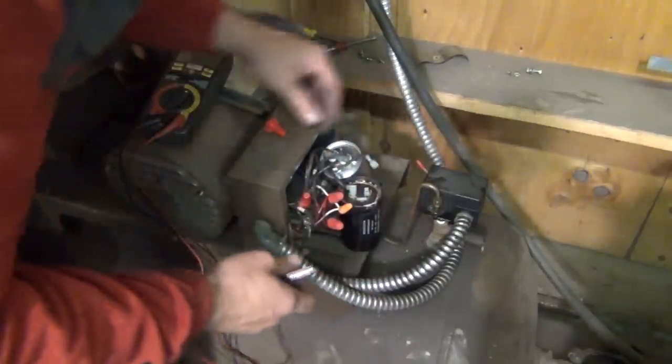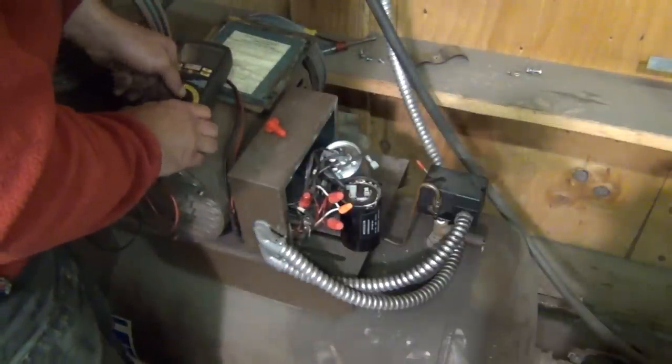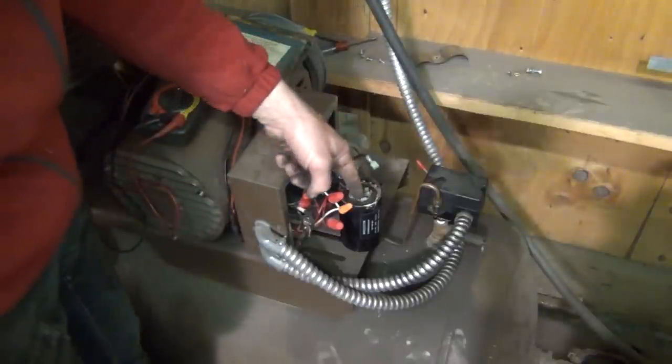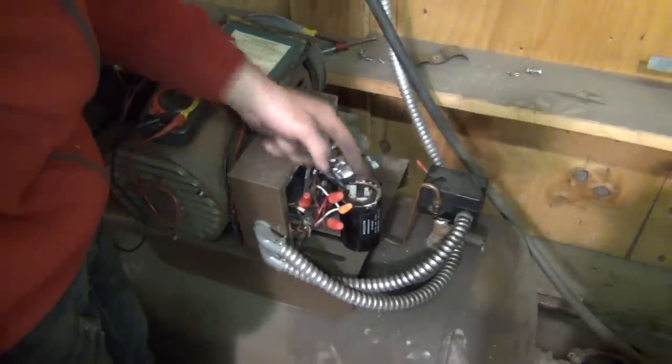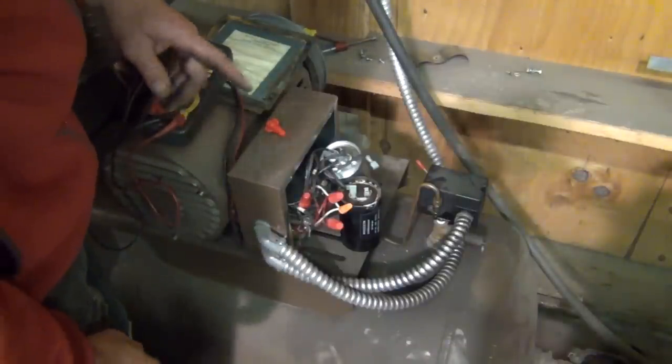We can actually verify that by setting up a temporary switch here. I'm going to go ahead and rig up a temporary switch, so I can manually put this capacitor in the start circuit, and if our motor comes up to speed, then we'll know that it's actually the inertia switch and not the capacitor.